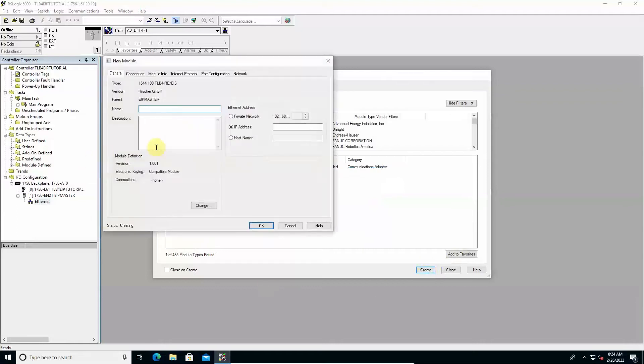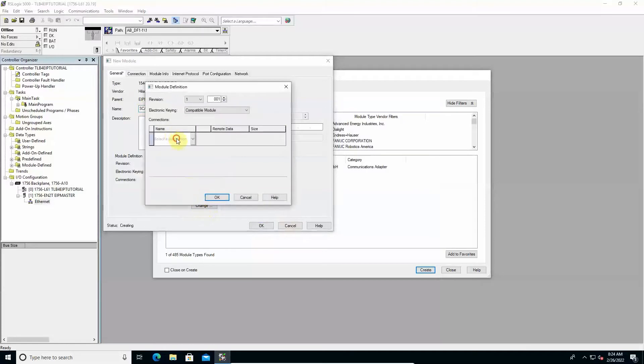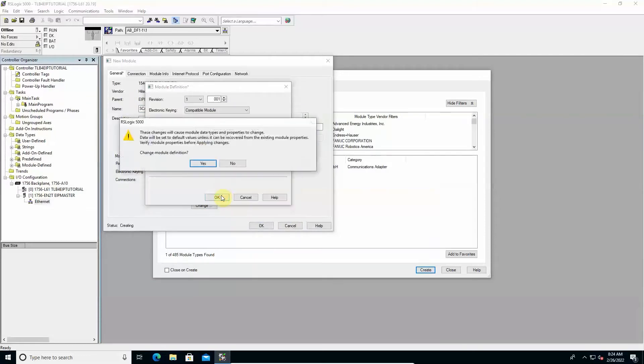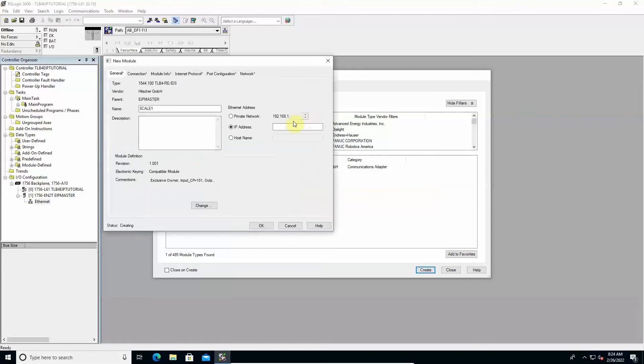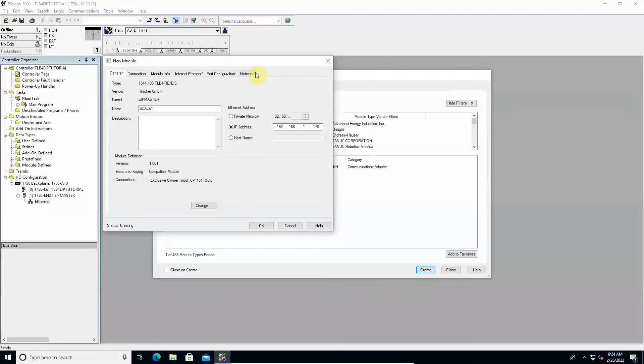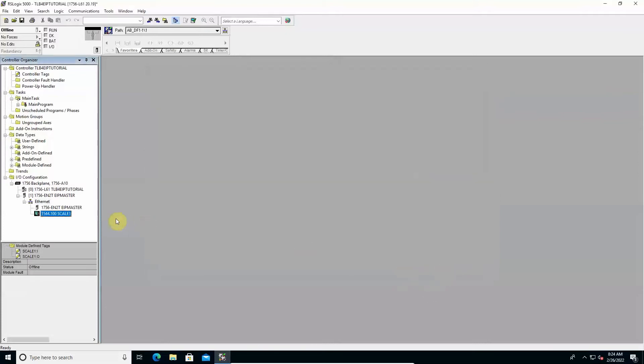A window opens to specify the module configuration. Fill in the module name, for example Scale1. Click Change. Select Exclusive Owner as Communication mode to set the cyclic data exchange with the PLC and click OK to return to the previous window. Set the address previously assigned to the TLB4 in the appropriate IP address field, 192.168.1.170. Click OK to confirm the settings and click Close to return to the main window.